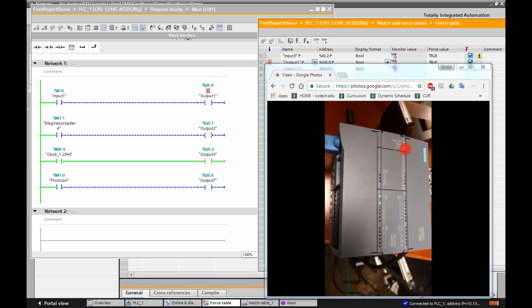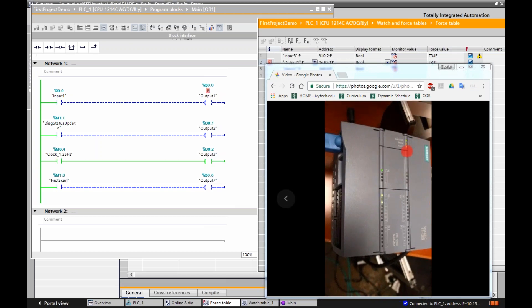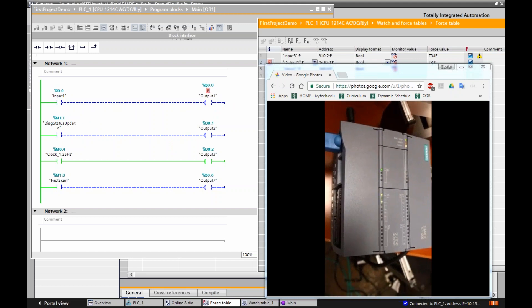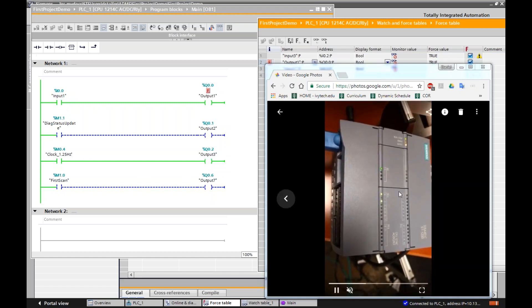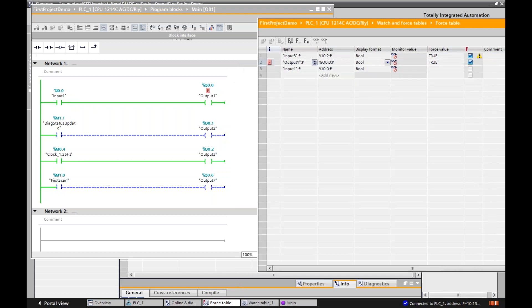You'll notice that up here the run/stop is green, but the maintenance is orange — and that's what happens with the force. The force will turn on the output, but it's just overriding what the logic is saying. So if I toggle this input, it's going to continue to run regardless. There is no logic affecting it — you're forcing something on.